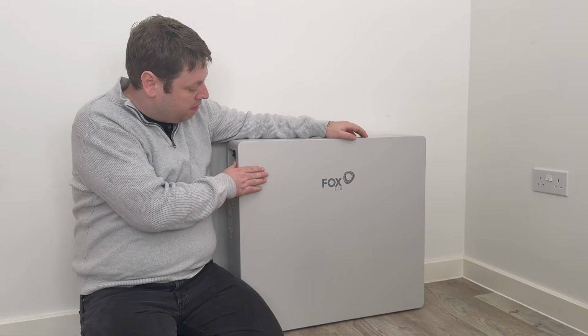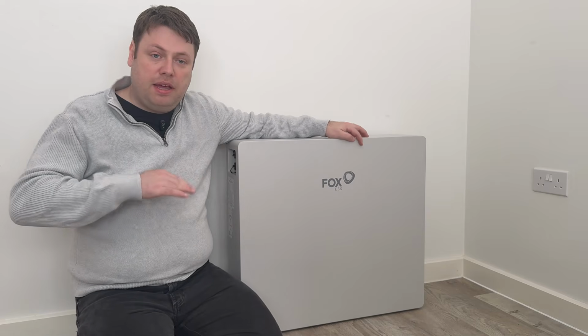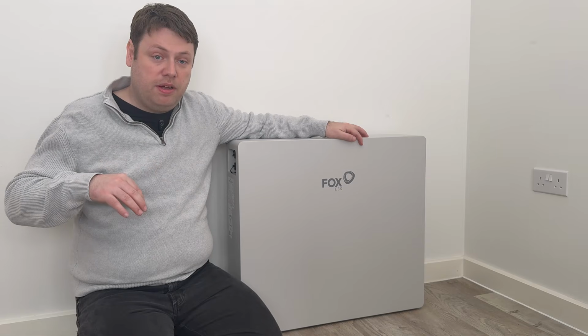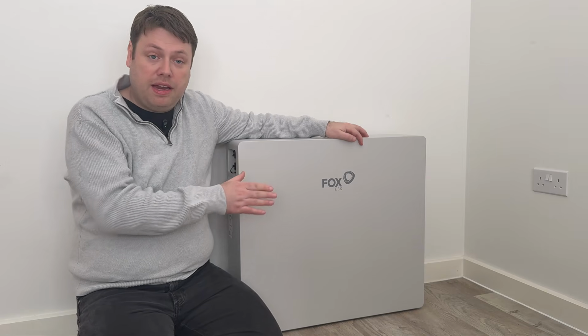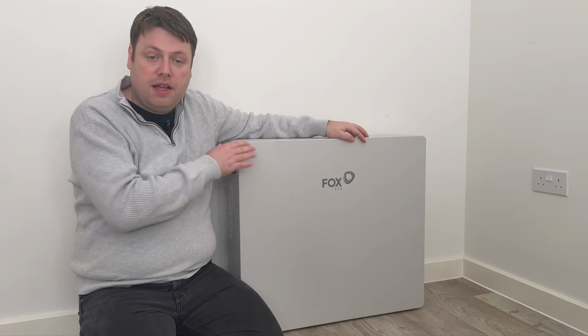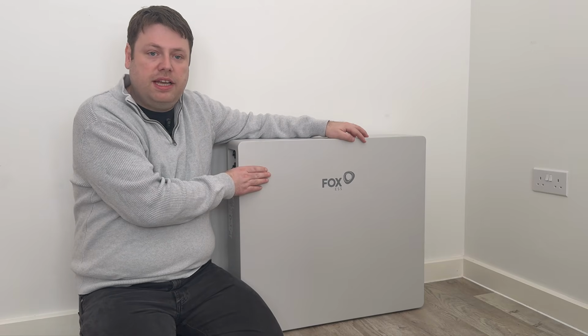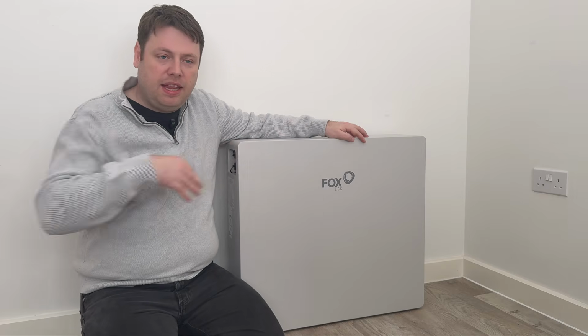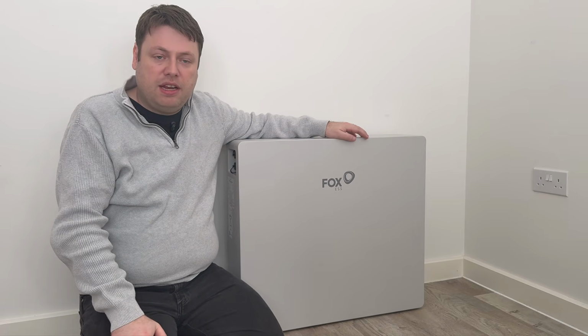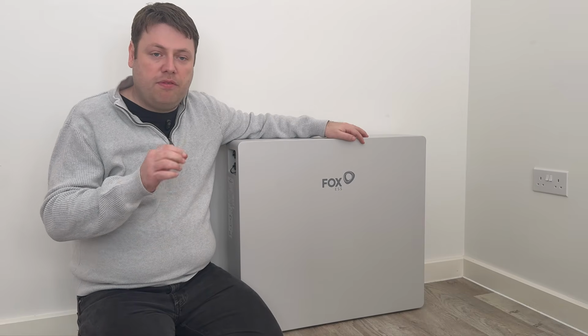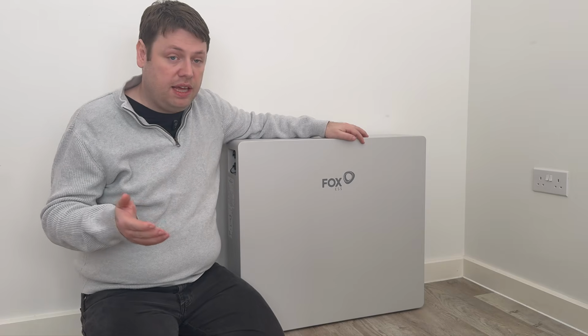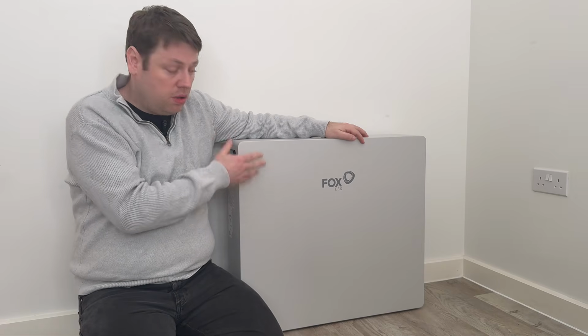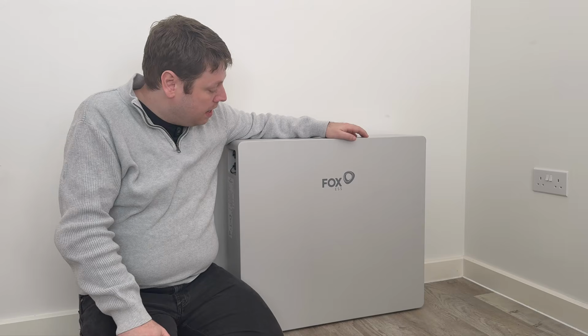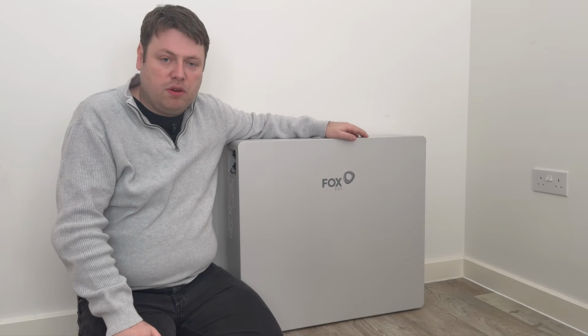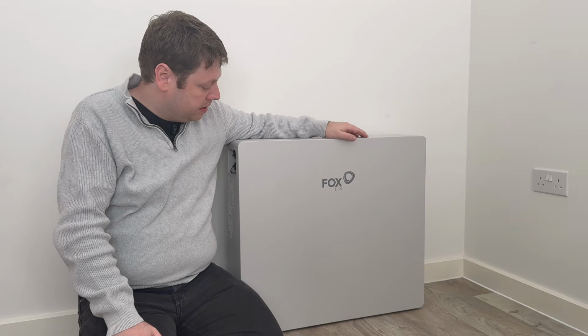So if I was to add this module to an existing EP11 non-heated customer, and we expanded with an additional EP12 Plus, this would lose its heating capability, because everything in the installation has to either be heated or not be heated. You can't mix them from a compatibility perspective. You'll just lose the heating functionality, but the battery will still work as a storage device. I'll link the tech article, which explains it far better than I just did.